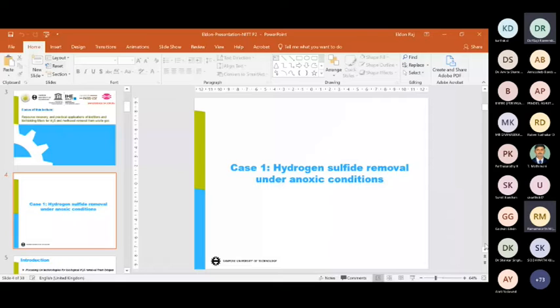But you all have to understand that even for an anaerobic digestion system or any anaerobic process, the biogas that is produced cannot be used as such in any natural gas grid or directly for electricity production, because it has a lot of impurities like hydrogen sulfide, siloxane, oxygen, water vapor, humidity, and so many different compounds that are present together with the biogas. So if you want to use biogas, there are some regulations for that.